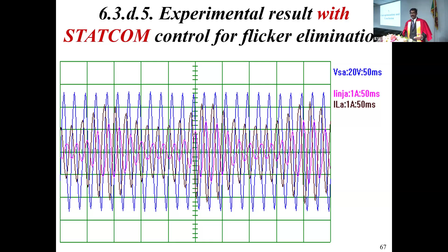A 225 megawatt STATCOM was implemented as the first STATCOM in the United Kingdom in 2000. Whenever you upgrade the rating, the resistor and inductor components become much smaller, so the response becomes even faster, since R and L become very small. You can achieve response within a couple of milliseconds. That's what I mean - whenever we think we need frequency response in seconds, we can simply reach it, because power electronic devices are geared to respond within a few milliseconds.